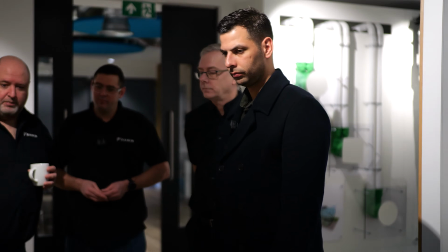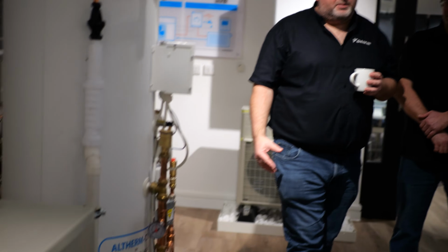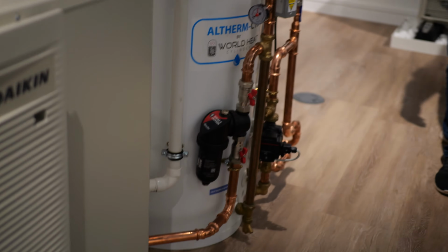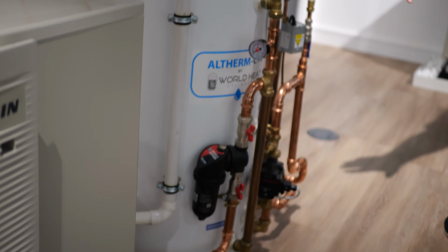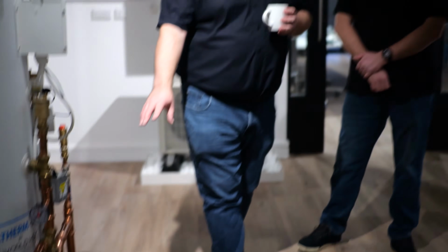You've got the low temperature monoblock - this is probably one of the most popular units we sell. We also do an option with the monoblocks with a pre-plumbed cylinder. What's nice about this is it's great for retrofitting, especially when you've got small bore piping, because the buffer tank at the bottom is effectively being used as a low loss header.